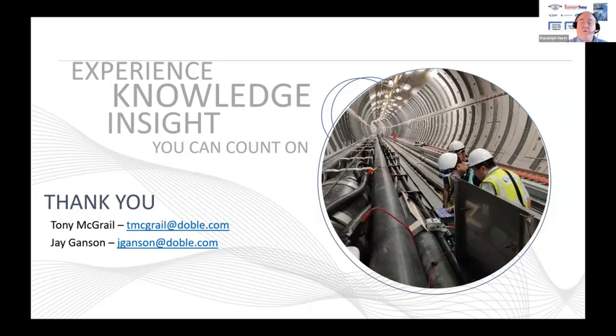Are the electrical losses greater for underground as opposed to overhead transmission? If you're thinking about traditional line loss, I'm not sure. Most of the studies that I've looked at that compare overhead and underground, even from a reliability and cost perspective, don't really weigh one way or the other as to what is the advisable solution. There are a lot of externalities to utilities that will drive them to decide to bury or hang lines overhead. So I'm not sure it's really a line loss cost, but from a condition monitoring perspective, it's the project cost and replacement cost that makes putting in a monitor for a small percentage of the actual project cost more attractive than for overhead. Okay.